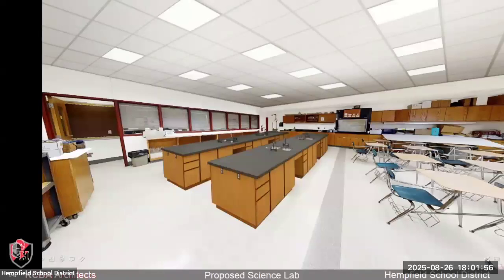I imagine that stays. Yeah, because the mechanical engineer term for this, in the old days, is called air changes per hour. In the old days, you wouldn't have had too many air changes per hour in the Buchanan science lab. Current code requires 16 air changes per hour in a science lab or food cooking lab, whereas a classroom is only 8. So it's automatically going to have twice the ventilation occurring in the room.